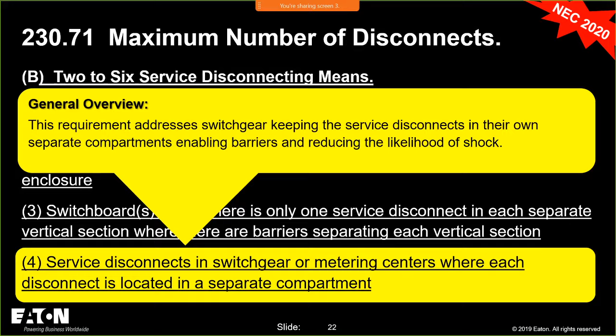The ability to barrier off and compartmentalize is not available right now in those meter centers, so the standards are trying to address that. I know they're working on some TIA language to help clarify that. They added informational notes reminding us that meter centers are addressed in UL 67, the standard for panel boards. The UL 67 STP and task groups have been looking at trying to figure out some language, but nothing's passed yet, so they're still working on that. I know there's also some energy around technical interim amendment efforts as well.